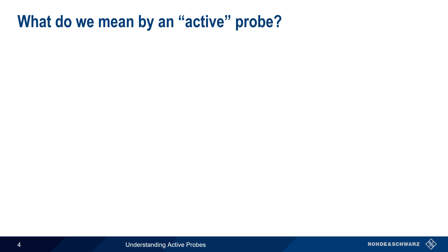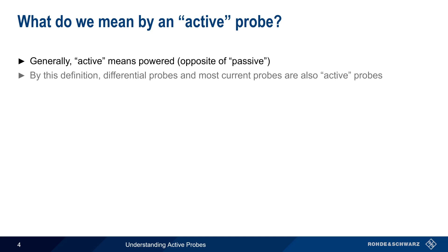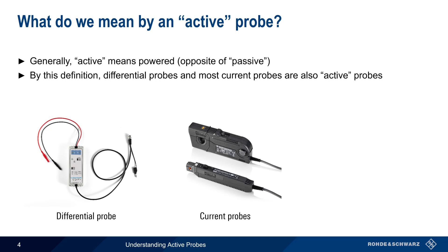So what is an active probe? Generally speaking, active means that the probe requires power. Recall that passive probes do not require a power source. Using this definition, differential probes and most types of current probes are also active, since these two types of probes also normally require power.